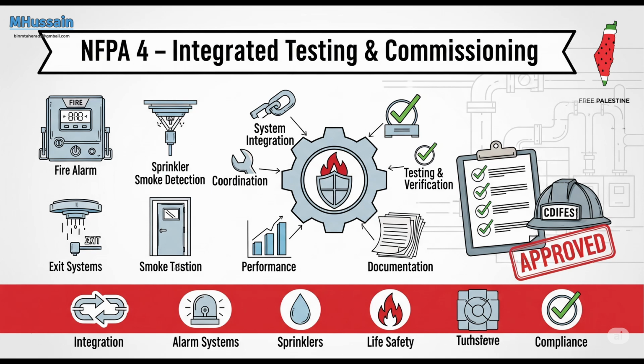Then you have periodic testing. These integrated systems require ongoing periodic tests to make sure they stay functional. The frequency is usually specified in that test plan we talked about. And what if it's an older existing system that never had a test plan or an initial NFPA 4 test because the standard is newer? Good point. For those existing systems, an integrated system test plan must be developed within 5 years of the standard being adopted by the local jurisdiction. And the first periodic test needs to be performed within 5 years as well, unless the plan itself allows for a different frequency based on risk or system type.